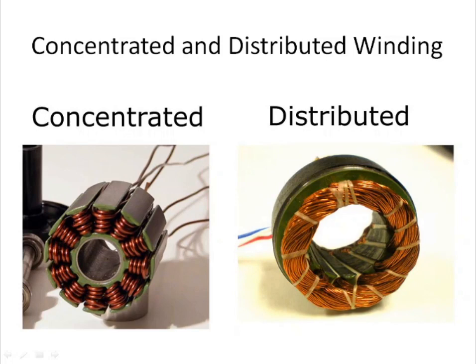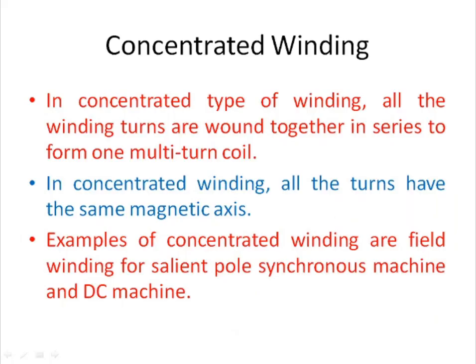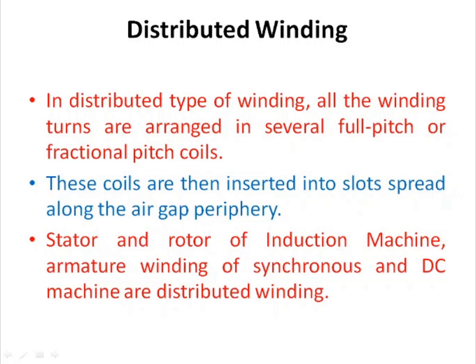Concentrated and distributed winding. This is the diagram of concentrated winding and this is distributed winding. In concentrated type of winding, all the winding turns are wound together in series to form one multi-turn coil, and all the turns have the same magnetic axis. In distributed winding, all the winding turns are arranged in several full pitch or fractional pitch coils along the air gap periphery.